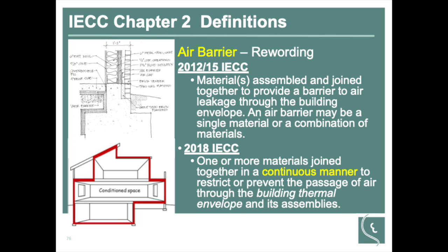I'm not fond of that either, so that's a hard detail to address. We were just asked that question not too long ago, and it's a very difficult detail. I'm not an engineer or thermodynamic person, but the code only requires you to go either 24 inches, 2 feet, horizontally or vertically. A lot of details you see, like this one here, go horizontally and vertically. If they did a 2-foot horizontal and vertical, they'll go up, then do an angle, then horizontal, but bring it down and they'll have that gap there.